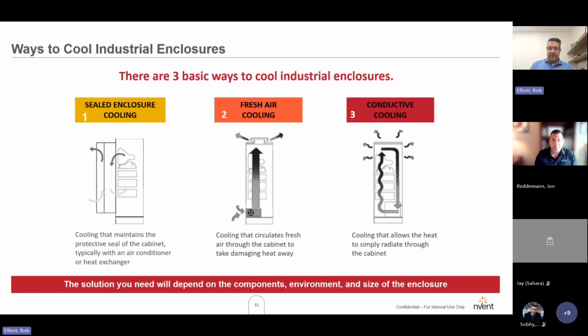Next slide, please. Yeah, and I'm sure, based on the environmental conditions and what you have going on, to your point, with fresh air cooling, what's the ambient temperature coming in, you're only going to get so much effect. And it seems like conductive cooling tends to probably be the methodology most people use right now. Yes, thank you for that, Rob. I have a lot of conversations with customers where they like to try to incorporate conductive cooling to minimize additional components, fans, filters, heat exchangers, air conditioners. And we have an online sizing selection program where we can run different scenarios to see how large of an enclosure we would need to dissipate 500 watts of heat.